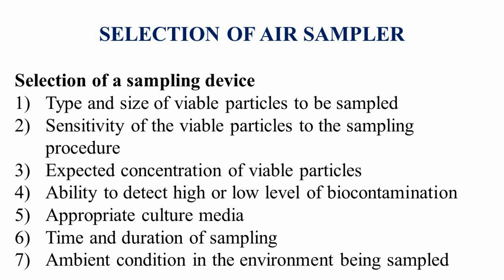Fifth is appropriate culture media. The sampler should not impact the culture media plate, and the plate shall be easily placed or removed. Sixth is time and duration of sampling. Time is very important because if the sampler continuously works it may lead to excess air sampling. To avoid this, proper time adjustment with auto on and off facility is also required in the air sampler.